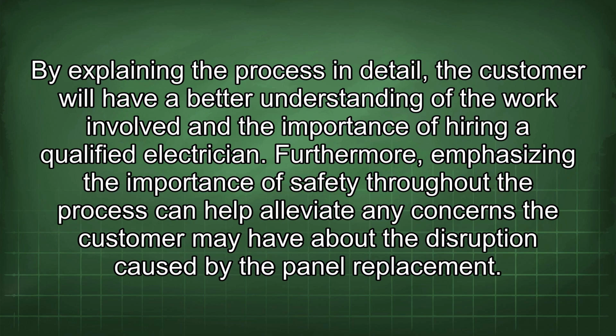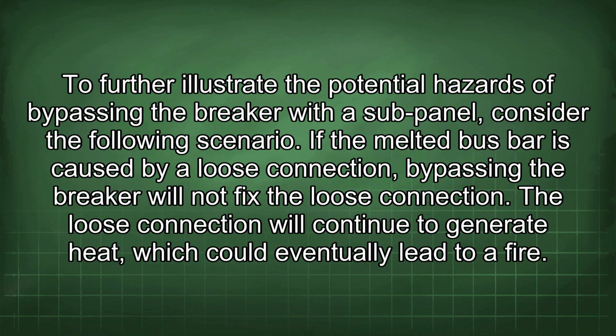Furthermore, emphasizing the importance of safety throughout the process can help alleviate any concerns the customer may have about the disruption caused by the panel replacement. To further illustrate the potential hazards of bypassing the breaker with a sub-panel, consider the following scenario. If the melted bus bar is caused by a loose connection, bypassing the breaker will not fix the loose connection. The loose connection will continue to generate heat, which could eventually lead to a fire.